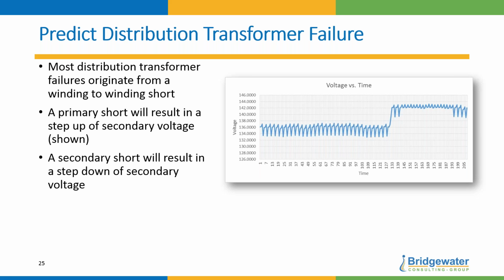That step change in voltage is your simple indicator. If it goes up, that's a winding-to-winding short in the primary. If it drops, it's a winding-to-winding short in the secondary. These winding-to-winding shorts are precursors. The transformer won't often fail outright, but it gives you a handle on knowing you better go out and do something about it, especially if it's in a wildfire area or a highly populated area.